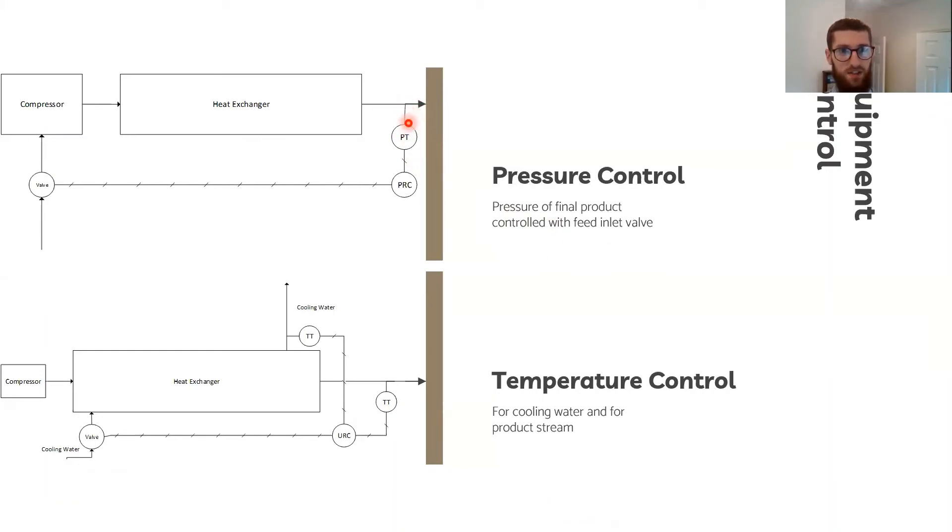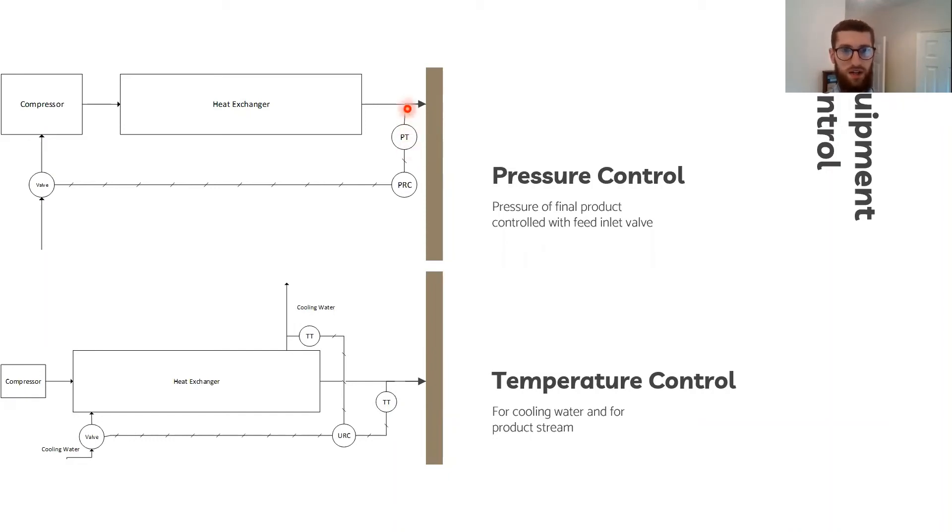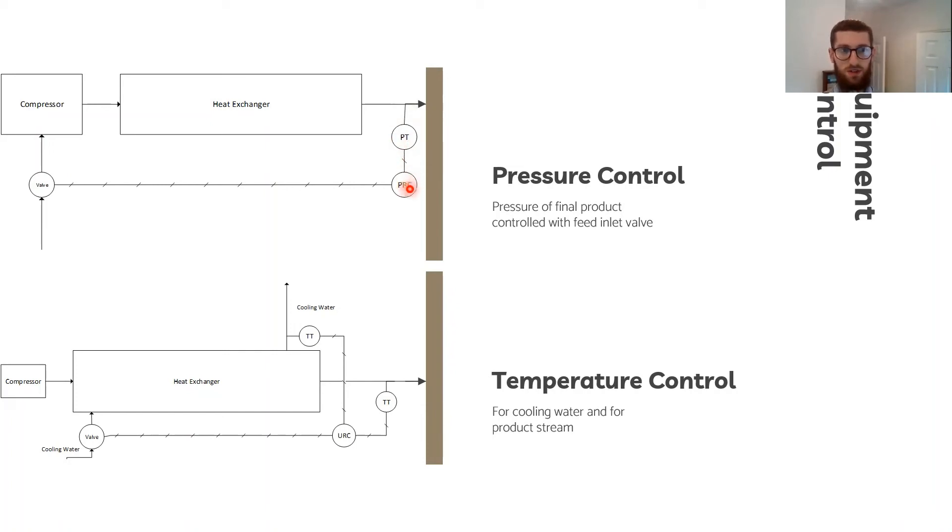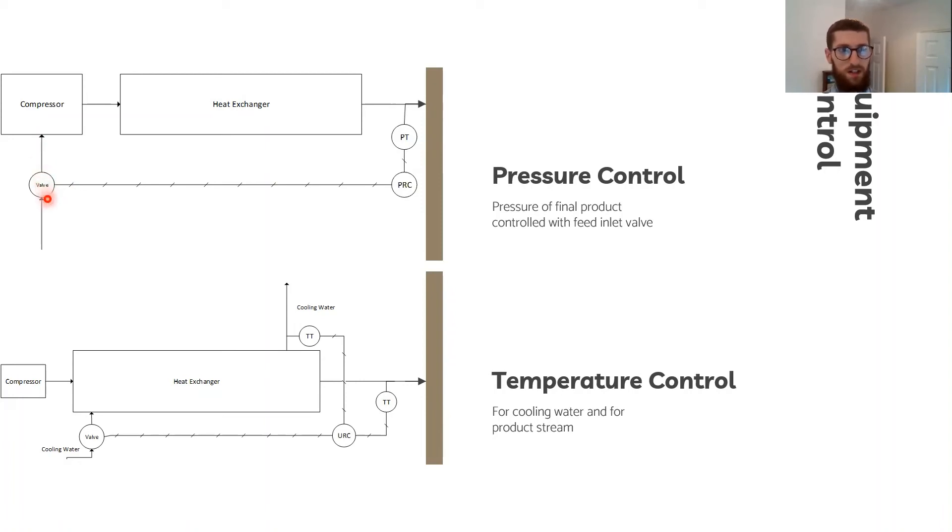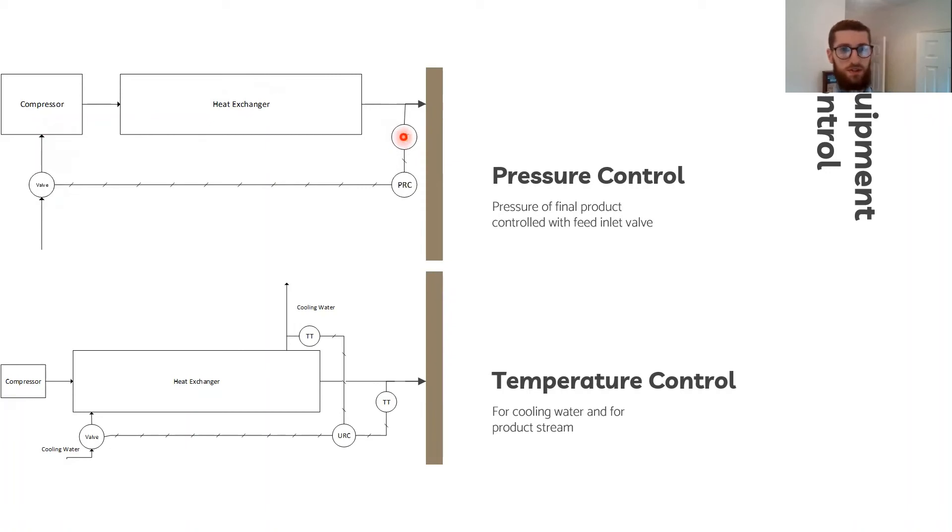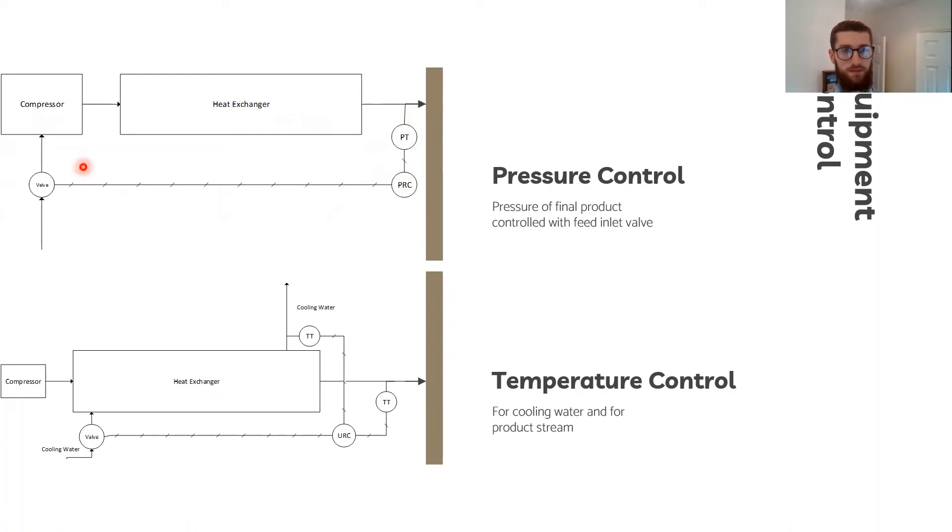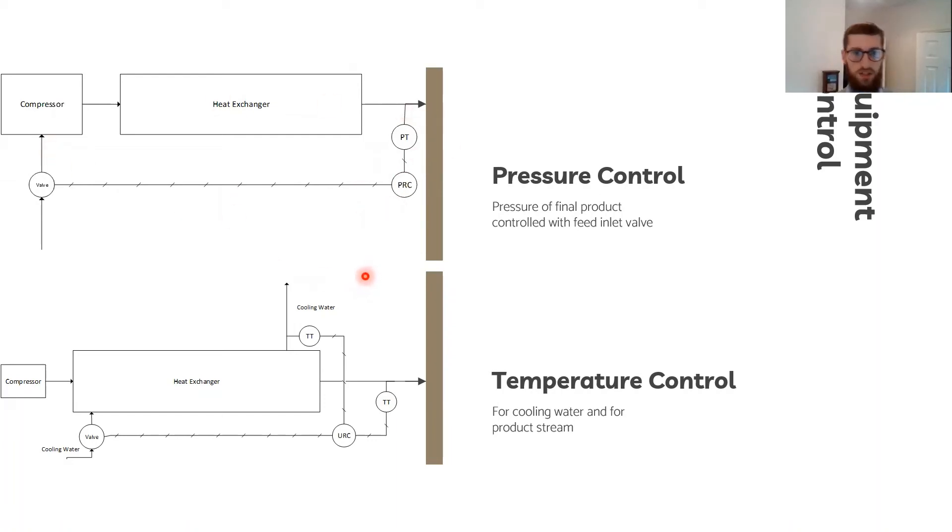A pressure transducer is used to detect the pressure. I used a strain gauge that sends a signal to a pressure controller, which controls the valve pneumatically of the inlet feed to the compressor, and that's used to control the outlet pressure in a continuous feedback loop of control, a feedback controlled regime.